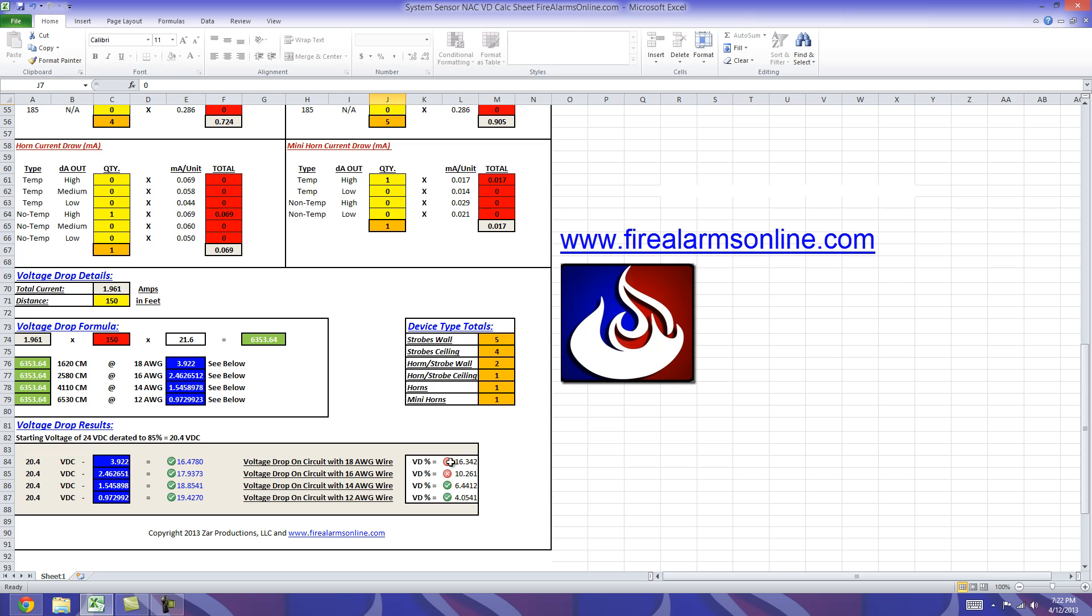So as you can see with 18 and 16 gauge wire we're exceeding the 10% voltage drop so we have a red X here which lets us know that with these values we've entered and the distance that we chose we have an option of either running with 14 gauge wire or 12 gauge wire. Either one will work.